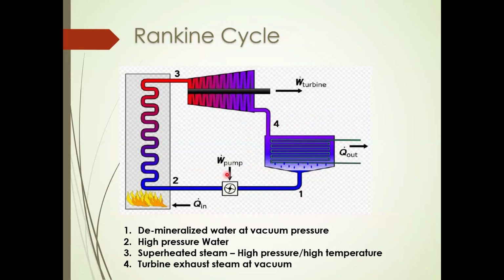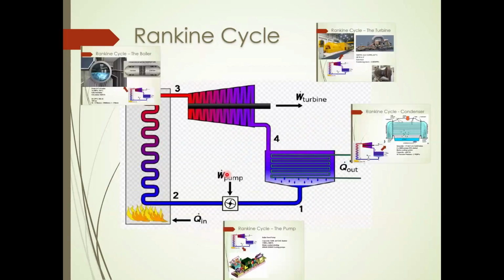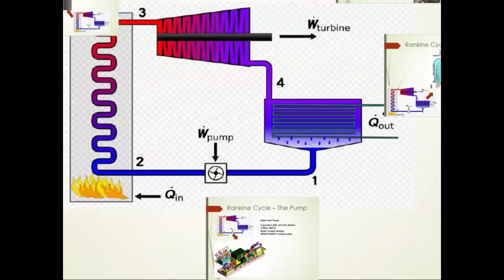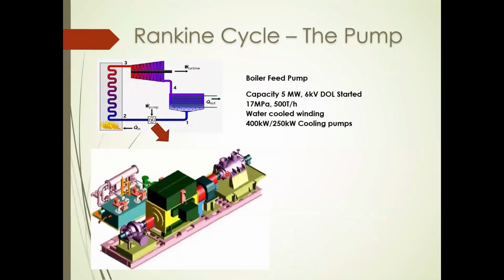Now, I will briefly explain the major equipment used in each phase, and their parameters and properties. These items will later contribute to our blackout explanation. The first stage is the pumping phase. As the name implies, there are pumps in this phase. Out of these pumps, the boiler feed pump, as the name implies, feeds water to the boiler.